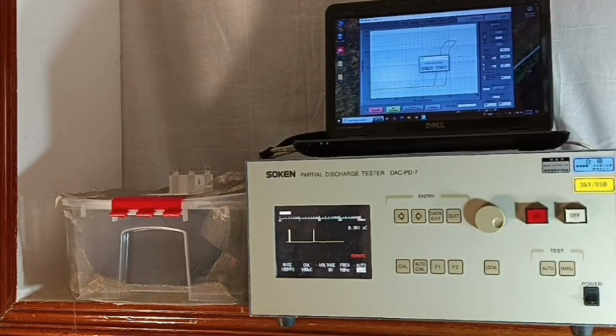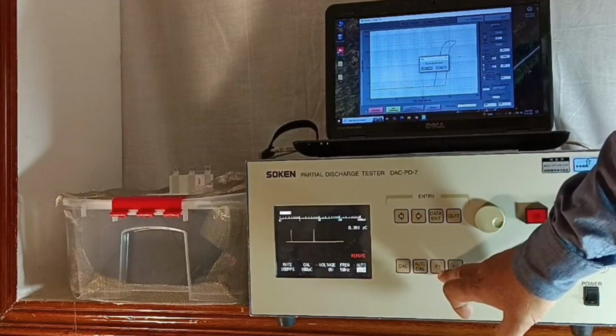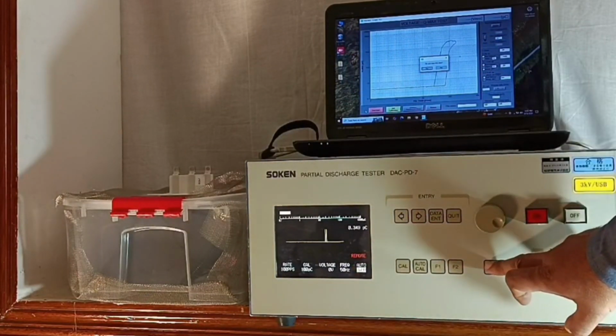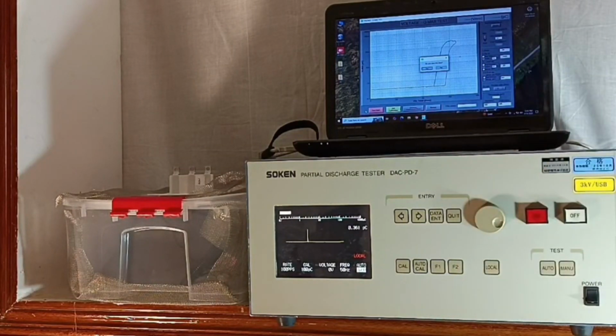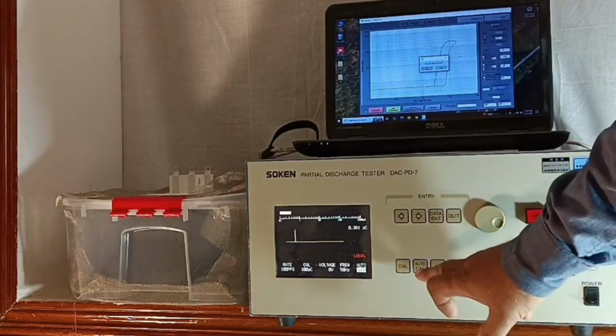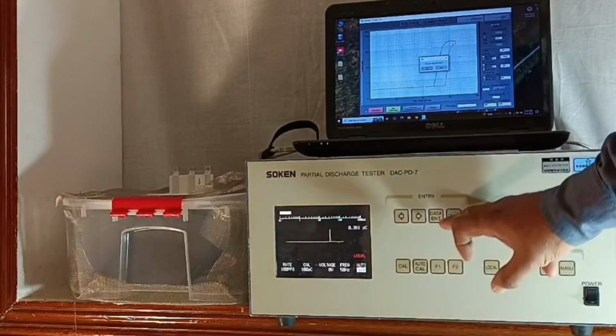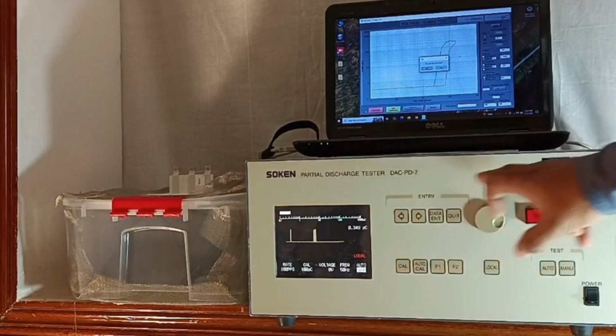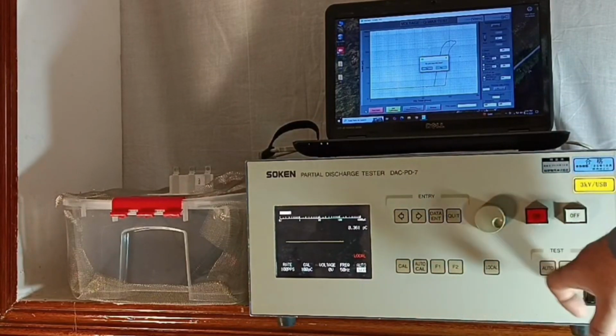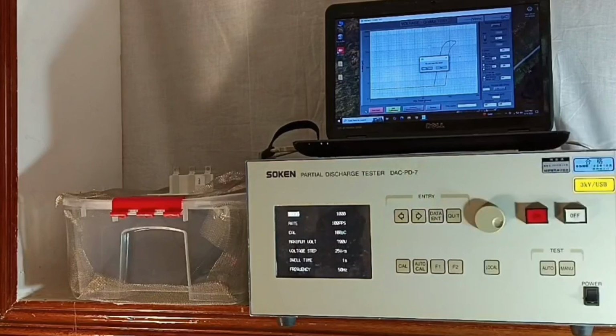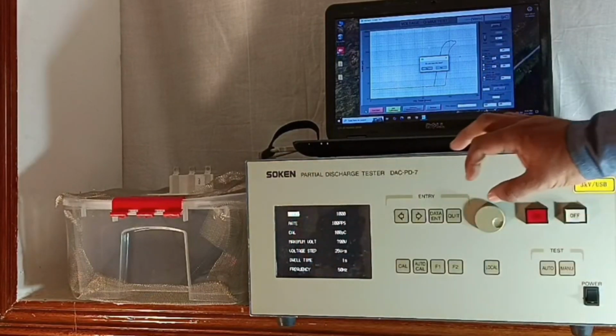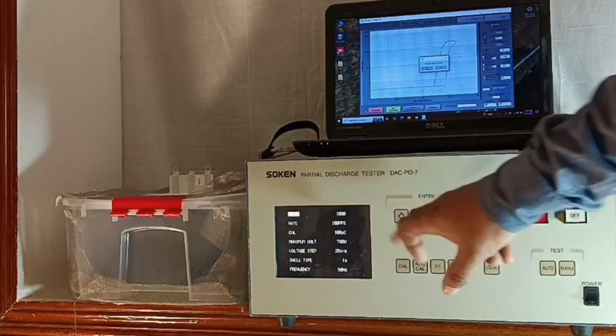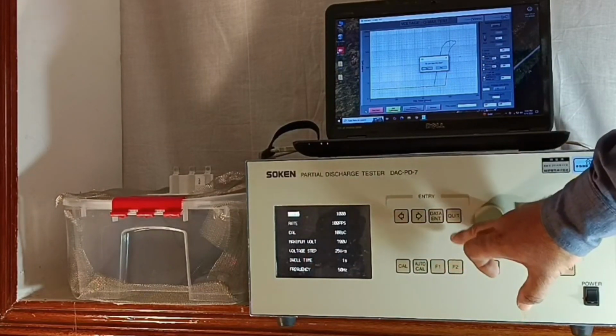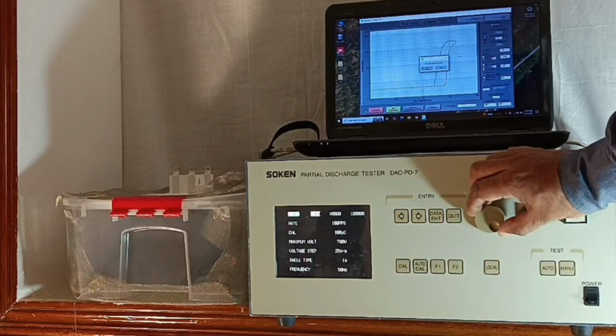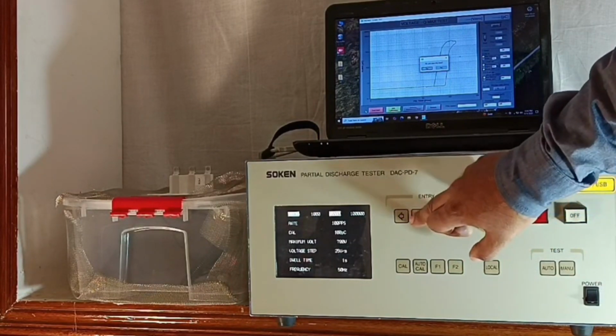This is a twisted enamel wire, round enamel wire. You can come to local, that is from the remote, you can come to local. Here you can do the autocal, the calibration, you can do it, or manual cal also you can do it from the panel here. Auto test, manual test. Now manual test is included. Data entry available. You can select the range. Data entry again. Range is 1000 pC or 10,000 pC or 1 lakh.